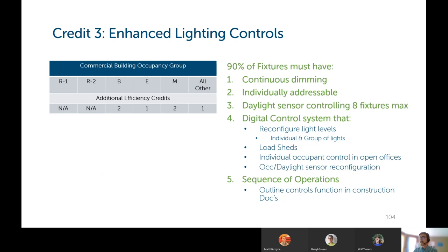The third credit is enhanced lighting controls. Residential buildings are not applicable for this, just the other occupancy types. 90% of fixtures must have continuous dimming, individually addressable fixtures, a daylight sensor controlling no more than 8 fixtures, and a digital control system that reconfigures the light levels individually or as a group of lights. You can do load shedding, individual occupant control in open offices, occupancy daylight sensor reconfiguration, and a sequence of operations that's outlined in the construction documents. So a networked lighting control would be a system that would meet these requirements here.